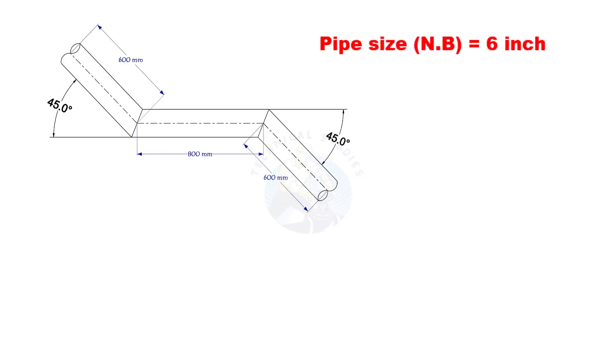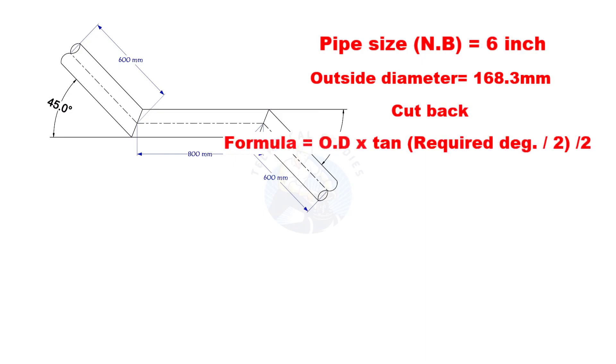The outside diameter of a 6 inch pipe is 168.3 millimeters. Cutback is O D multiplied by tan half degree divided by 2. Here, the required degree is 45. Half of 45 is 22.5.